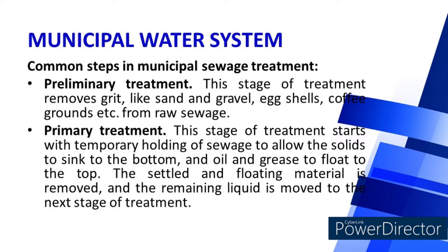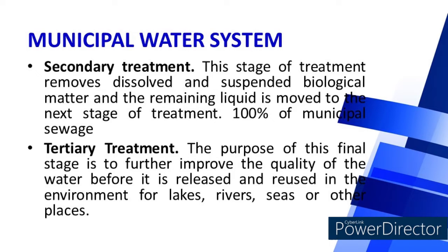After knowing the five key stages, let us determine the common steps in municipal sewage treatment. First is preliminary treatment, which removes grit like sand, gravel, eggshells, and coffee grounds from raw sewage. Next is primary treatment, which starts with temporary holding of sewage to allow solids to sink to the bottom and oil and grease to float to the top. The settled and floating material is removed and the remaining liquid moves to the next stage.